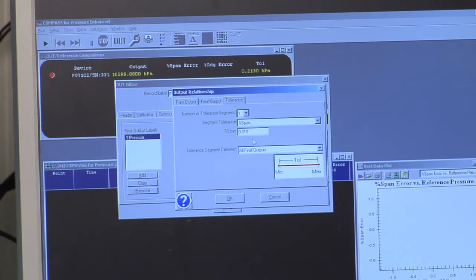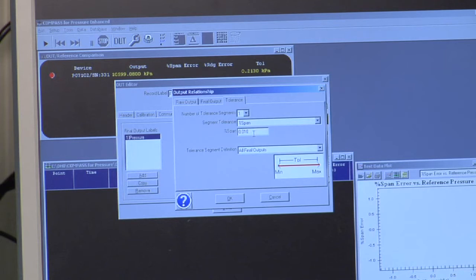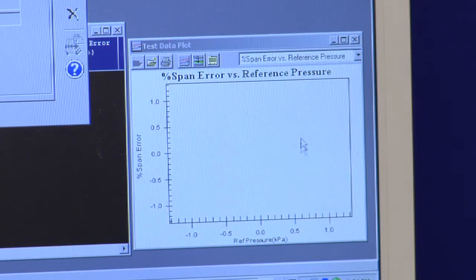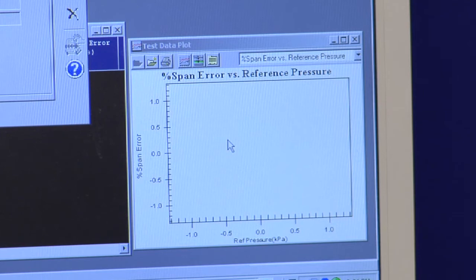And finally, I have a tolerance. By defining a tolerance, I can real-time determine if the instrument is in or out of spec while the test is running. This plot at the bottom will be updated with tolerance bars and the error. And if the error exceeds the tolerance, you'll know graphically while the test is running.